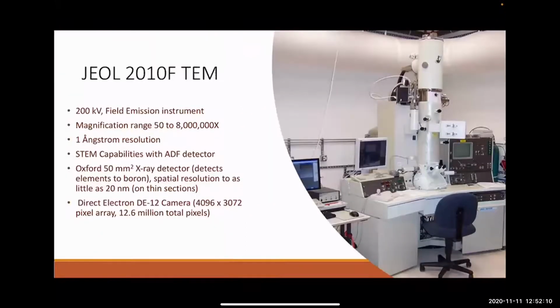And then our best, if you will, microscope. This is a field emission microscope and a 200 kV instrument. It's our JEOL 2010F. And this is the one that can get down to atomic resolution fairly easily. It has, you can't see it, it's off to the side, but it has X-ray EDS as well, and has STEM capabilities. And also, I haven't really talked about detectors today or camera systems, but it has a direct electron camera, which is a state-of-the-art imaging system that can actually provide its own resolution bump.